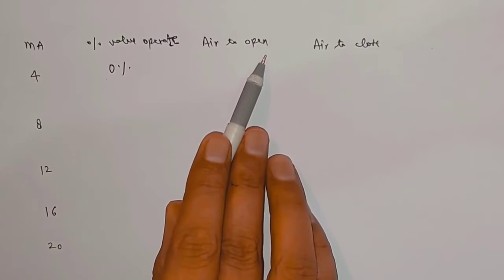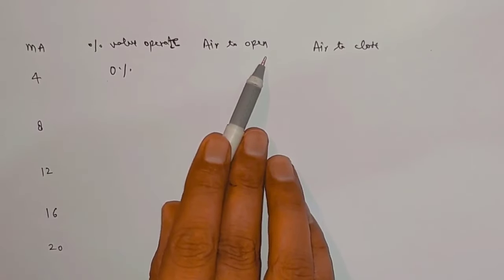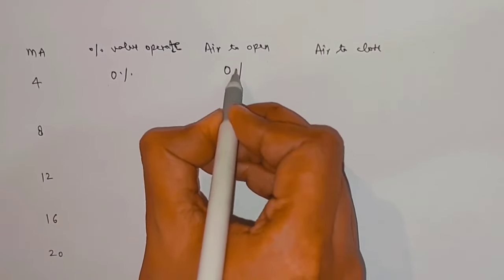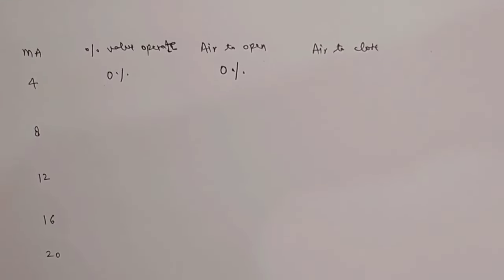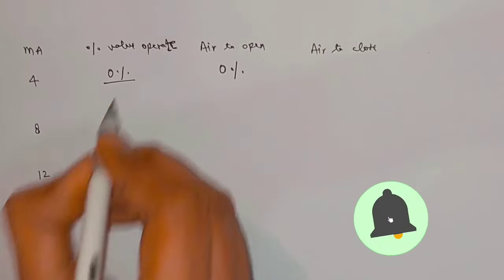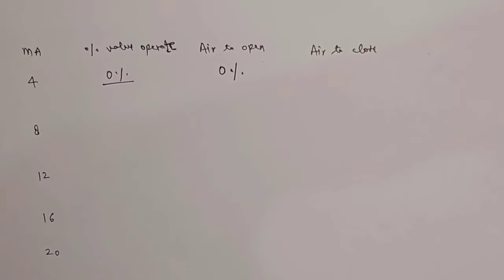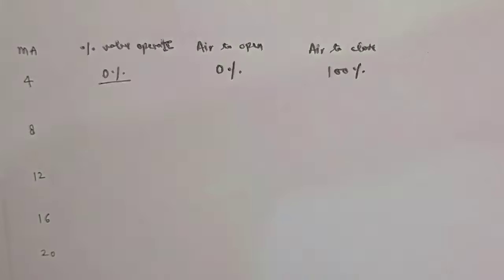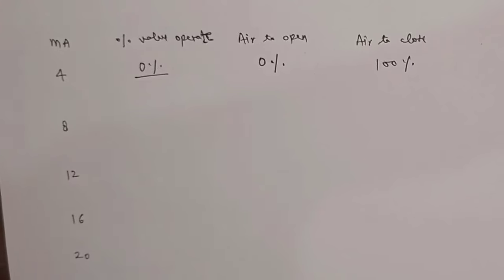When we take the air-to-open control valve and it operates 0%, its percentage opening will be 0%. But when we take the air-to-close control valve and it operates 0%, then its opening percentage will be 100%.